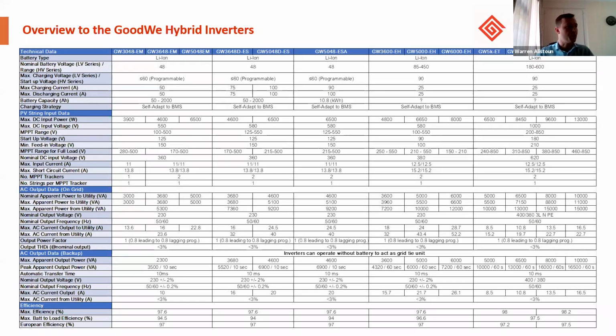So just an overview of the hybrid family. We can see that there are three EM series. We've got 2 ES series inverters, 1 ESA, 3 EH products, and 4 ET products. All products are lithium-ion ready and self-adapt to the BMS. What's critical when considering these inverters is our battery voltage, to select the right batteries, as the high voltages differ from the low voltages. What's also worth noting is the backup power presented by the different family of products. So understanding which products can deliver the energy required for your appliance loads is very important. And as you can see, we deliver from 2.3 kVA all the way up to 10 kVA.